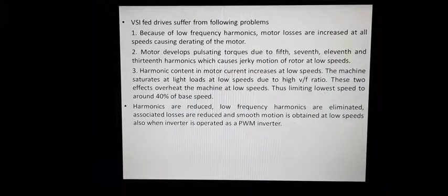Due to the presence of these lower order harmonics, there used to be pulsating torques and the machine losses also used to be comparatively high. So this all results in the derating of the machines, and it is even very difficult to achieve smooth speed control at lower speeds.